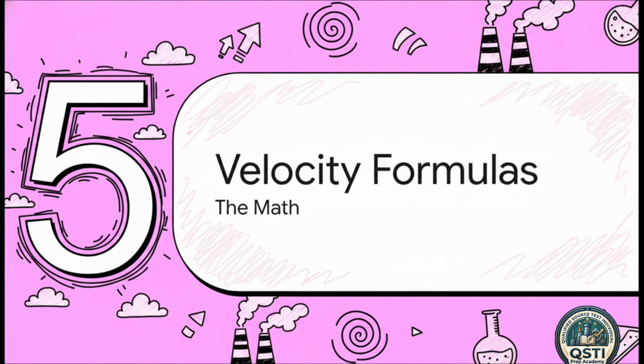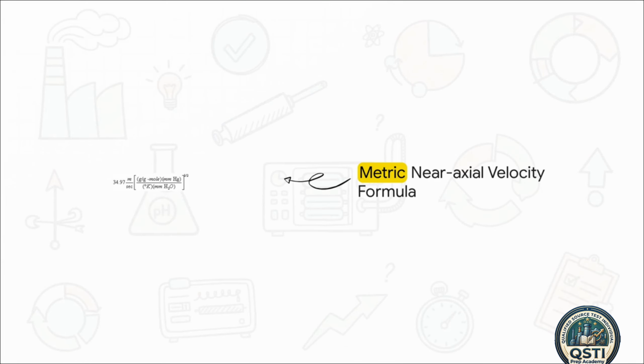Section 5, Stack Gas Velocity Formulas. The math. Let's get into it. Focus in on the top half of your screen for the absolute highest priority formulas you'll need for test day. Watch this metric near-axial velocity equation draw out. Notice that 34.97 constant? You take that, multiply it by the pitot tube coefficient Cp, and see how the square root of the differential pressure, when you combine it with absolute temperature, pressure, and molecular weight, drives the whole near-axial velocity? Oh, and don't forget, you also incorporate the cosine of that yaw angle you just measured in the field to finalize your correction.